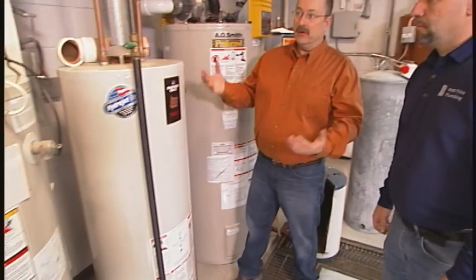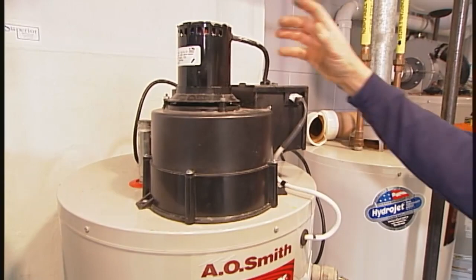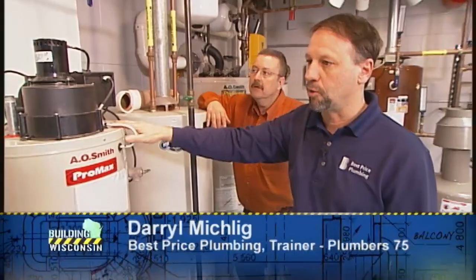Okay, on this case right here we have a B-vent gas water heater, which means this vent goes all the way up through and out your roof. So on this particular model, you need to vent it all the way out the roof. If you have a power vent water heater, like this one, you're going to have a blower motor on top that takes the gases and sends them through a PVC pipe out the side of your house. An electric water heater has no venting at all; it just has electric elements on it. So there are different types to be aware of out there.